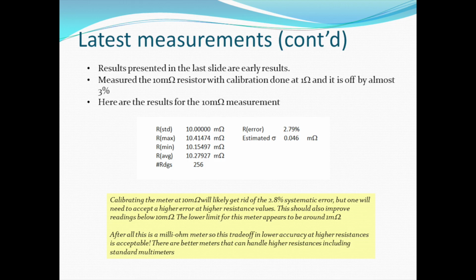I do have a better temperature setup that I'm building right now, and I'll probably describe that in a future video, and that will allow me to go over a slightly larger range with more accurate temperature control. So I think these are fairly decent results, 3% at 10 milliohm. I think I could maybe bring that down to close to zero, then I'd probably get better results at even lower milliohm values, but accept slightly higher errors at higher values. But then other meters which are designed to operate at higher resistance are probably more accurate and designed for that, so I am not too concerned about that. This specific application requires milliohm kind of accuracy, so that's where this meter will shine, I think.